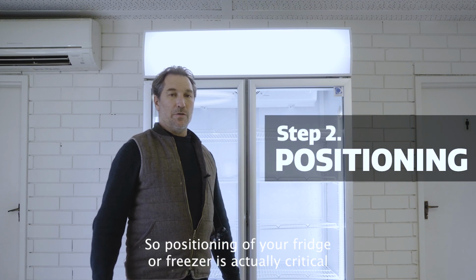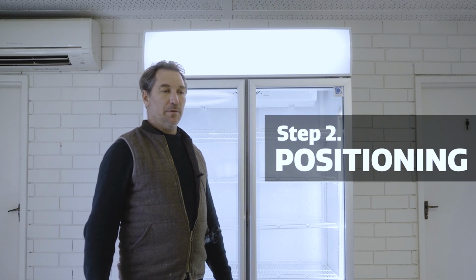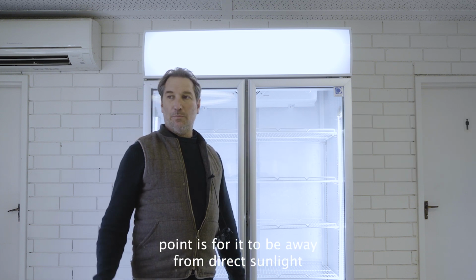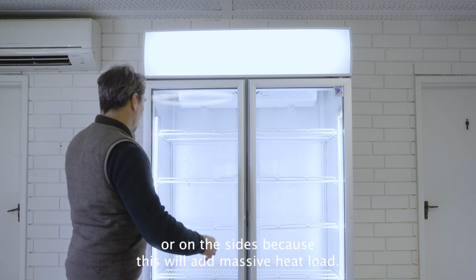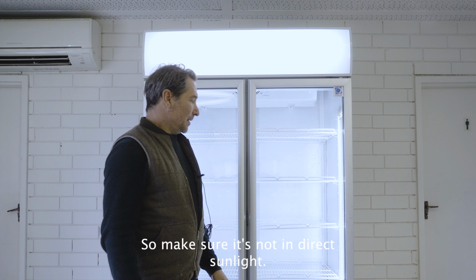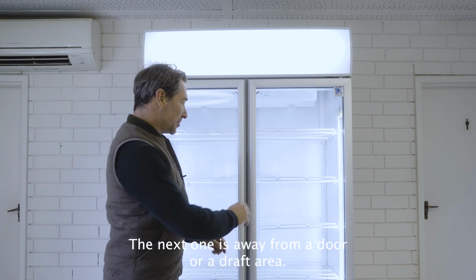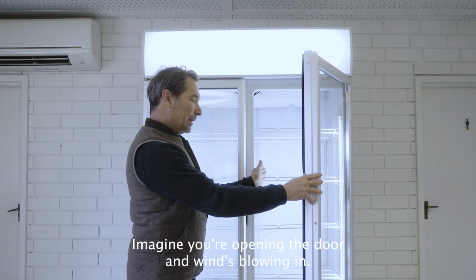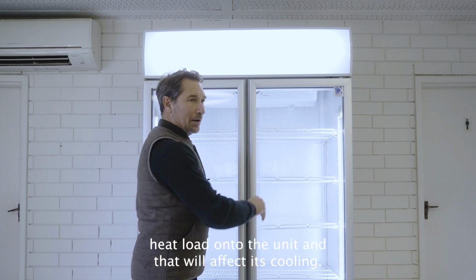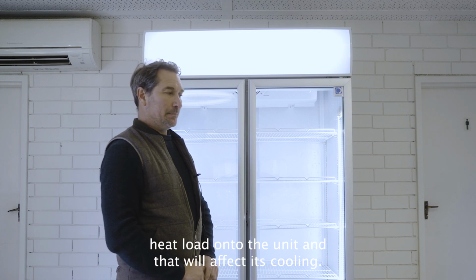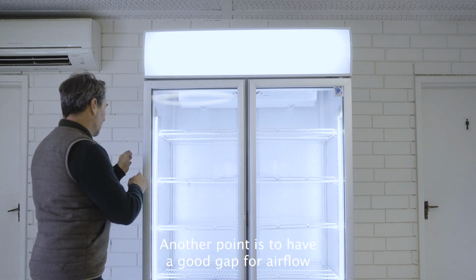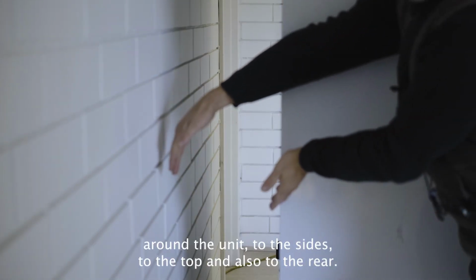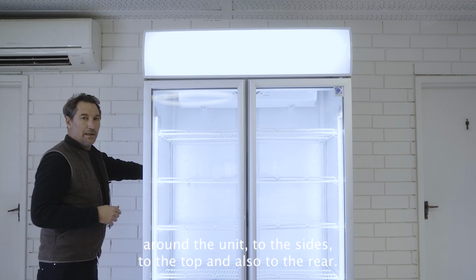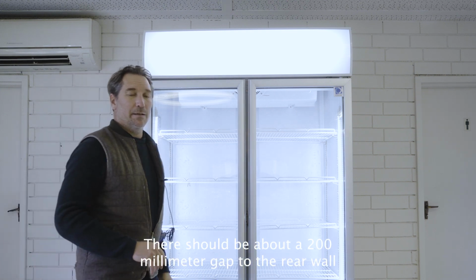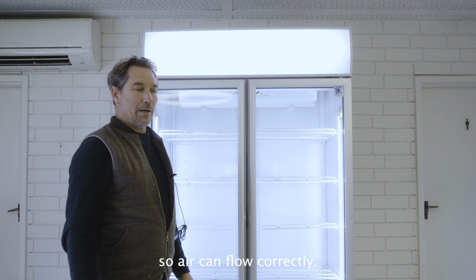So positioning of your fridge or freezer is actually critical with its performance. The first point is for it to be away from direct sunlight entering the unit or on the sides, because this will add massive heat load. So make sure it's not in direct sunlight. The next one is away from a door or a draft area. Imagine you're opening the door and wind's blowing in. It's obviously putting heat load onto the unit and that will affect its cooling. Another point is to have a good gap for airflow around the unit, to the sides, to the top, and also to the rear. There should be about a 200mm gap to the rear wall so air can flow correctly.